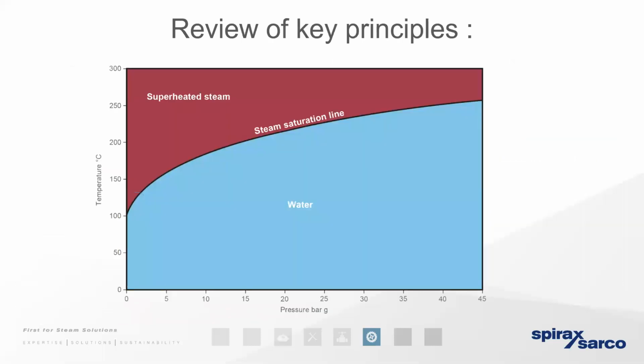So let's just remind ourselves about that pressure-temperature relationship. We know that there's a direct temperature-pressure relationship with both the steam and the condensate, and we know that when steam condenses, it gives up its latent heat energy, but it doesn't give up any temperature. So we can see that if we know the steam pressure, well, we know the temperature. For example, if we're generating steam at the boiler at 10 bar gauge, well, that's going to exist at a temperature of 184 degrees. But when steam condenses in the distribution pipework, especially if it's wet steam, that condensate that exists in the distribution pipework is going to exist at the same temperature and at the same pressure. It's just a different phase. It's a liquid as opposed to gas.